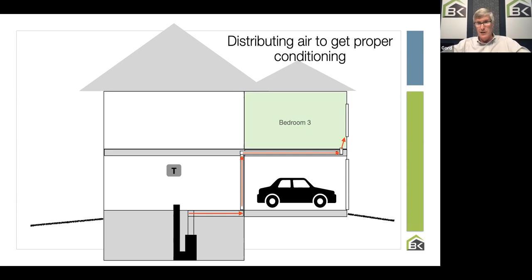That pressure is important to get the air to the room, specifically the longest run. If I have half the pressure, far less air actually travels to the end. So interestingly, the rooms that are closest, we have to balance those down to increase the pressure in the duct system so more air gets out over the end of the longest run. That's a huge comfort challenge.